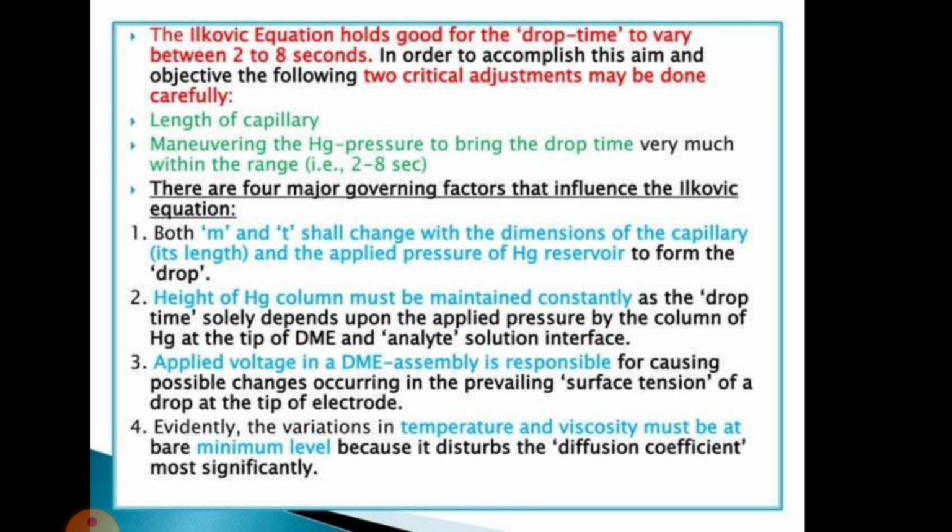The Ilkovic equation holds good for a drop time varying between 2 to 8 seconds. In order to accomplish this aim, the following two critical adjustments may be done carefully. First is the length of the capillary, and second is maneuvering the Hg pressure, to bring the drop time within the range, that is 2 to 8 seconds.